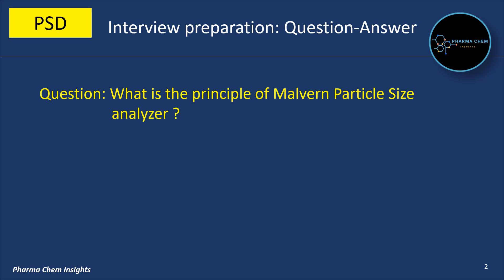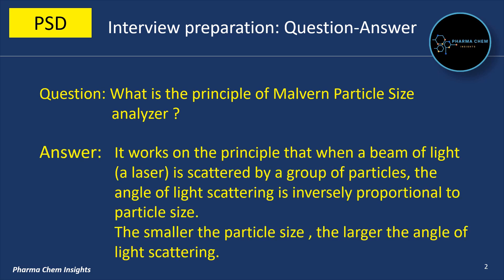First question: what is the principle of Malvern Particle Size Analyzer? It works on the principle that when a beam of light, a laser, is scattered by a group of particles, the angle of light scattering is inversely proportional to the particle size. That is, the smaller the particle size, the larger the angle of light scattering.